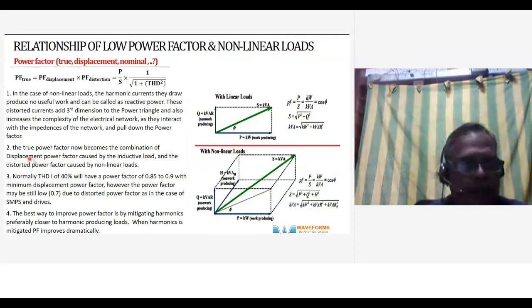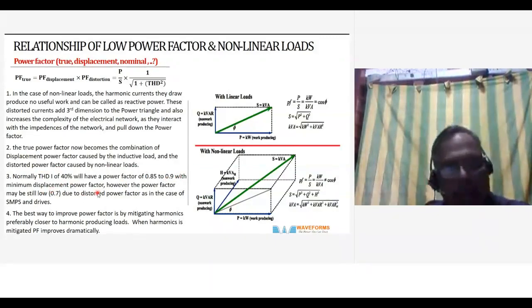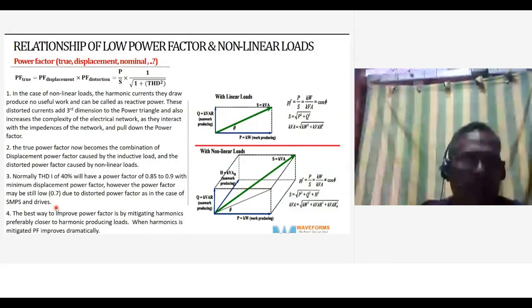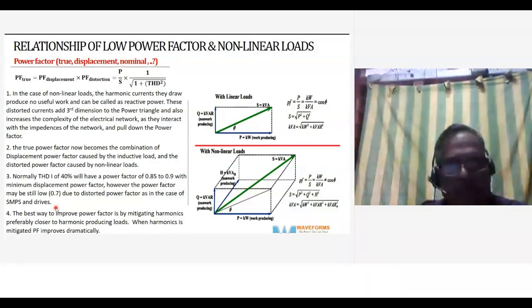The true power factor now becomes a combination of the displacement power factor caused by the inductive load and the distortion power factor caused by non-linear loads. Normally, with THD of 40%, you have a power factor of 0.85 to 0.9. Normally the power factor is good. However, the power factor may still be low due to distortion power factor in the case of SMPS and drives. In SMPS and drives, the power factor is normally 0.6 or 0.7. It is not because of displacement power factor, but largely due to distortion power factor.